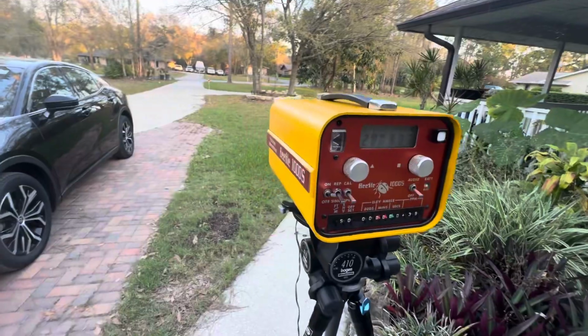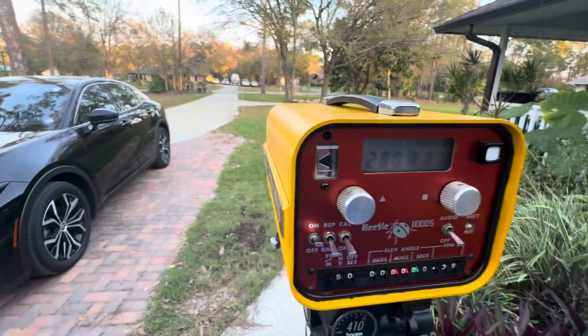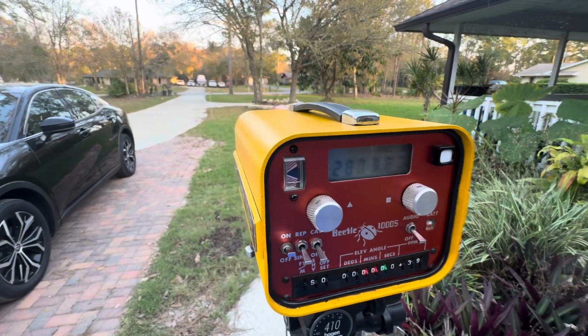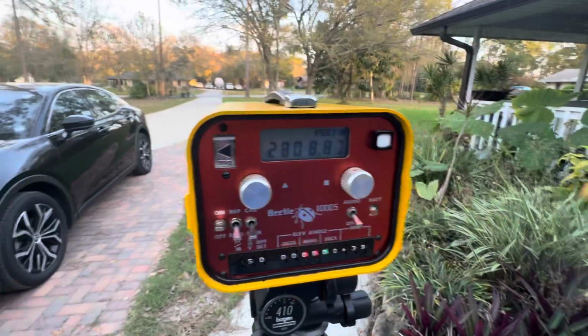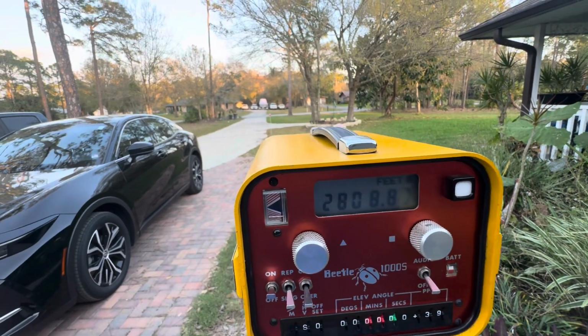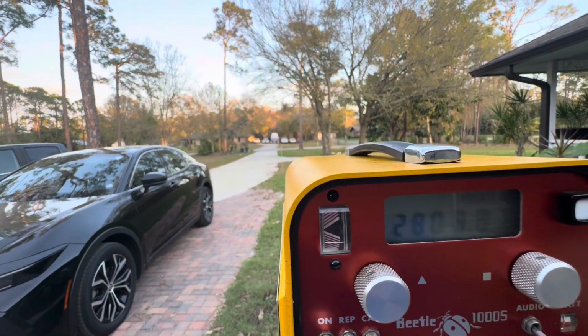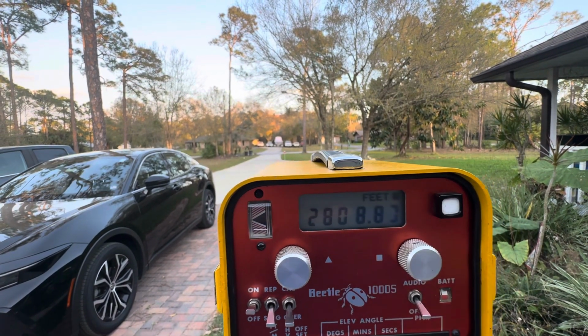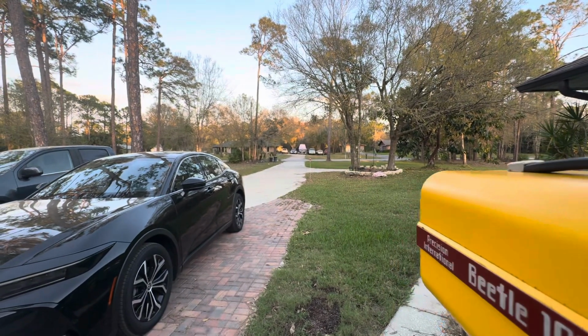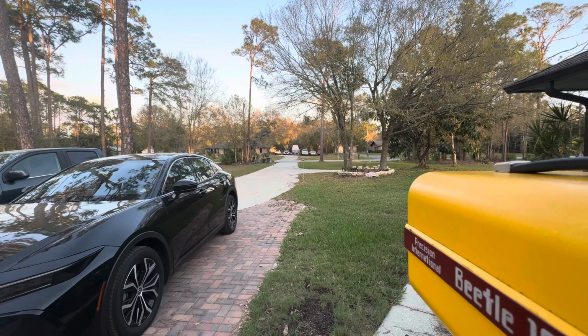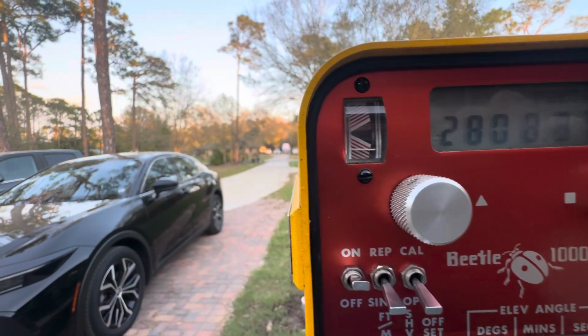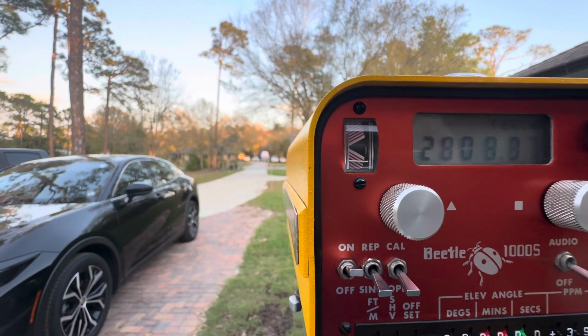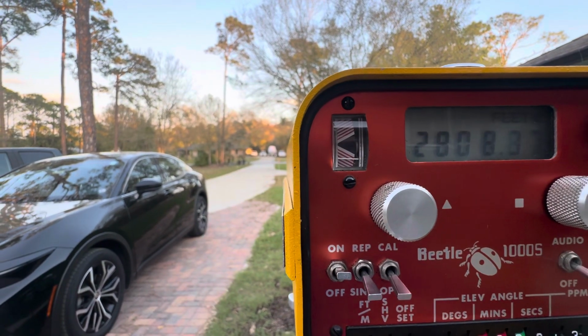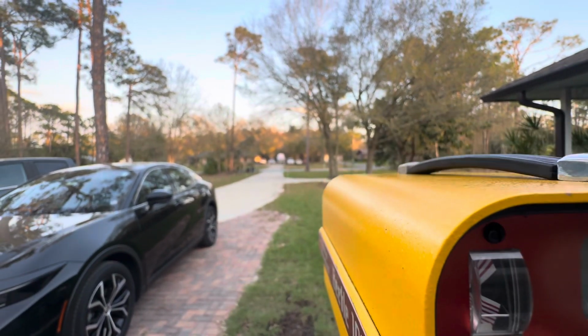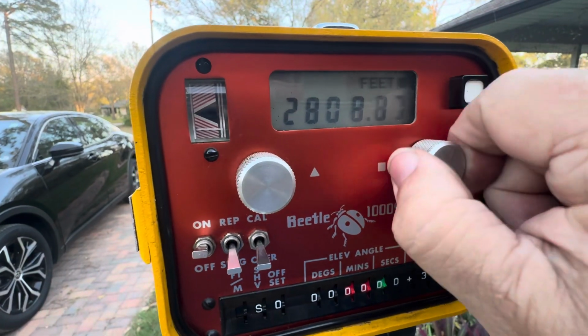Anyway, this works, and the way you would aim it on a theodolite, of course, you'd have it trammed in so that everything lines up with whatever you're looking at. But even just on a standalone tripod it is not too hard. What I do is I eyeball it vertically on the top of the reflector. And then I just go into the corner here until I can see the reflector. It's not going to focus on both, so I'm going to do it by eye real quick. And you'll hear it start. Oh, I flicked this to audio first of all and set the sensitivity to max. That's something you want to do while you're hunting for the target.